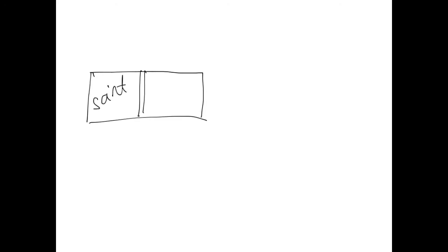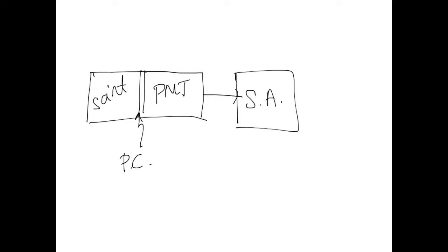Before we really get into this, I just want to remind you of the block diagram that we have for the scintillators. You recall that we have our scintillating material right here, and then we have the photocathode here, whose job is to convert light to charge. Then we have the photomultiplier tube, or a photodiode, and this is what amplifies that charge. Then this is going to be output into some sort of shaping amplifier like we've already described, and into our multi-channel analyzer, and this is where the spectrum comes from.